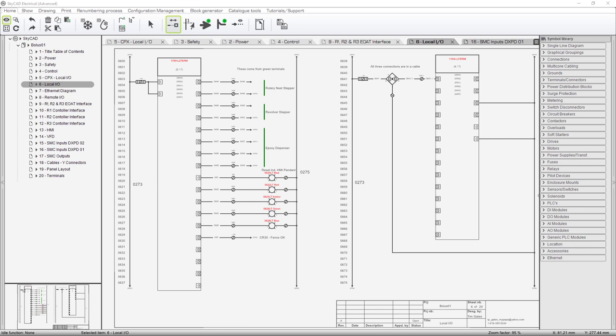So the fence okay simply means that I have inhibited all three robots and any other motion on the table, and I have gotten motion complete from all the elements that can move and cause injury, and then the fence okay signal is on. So that signal can go on any time it wants, if there's no motion on the table, and nothing is being told to move. And if the operator hits the entry permission button at the right moment, it'll let them in almost instantly. So that's what the fence okay is.